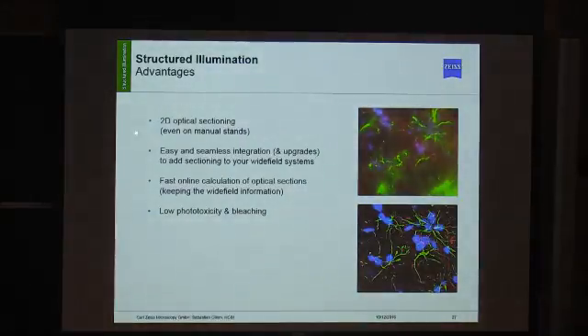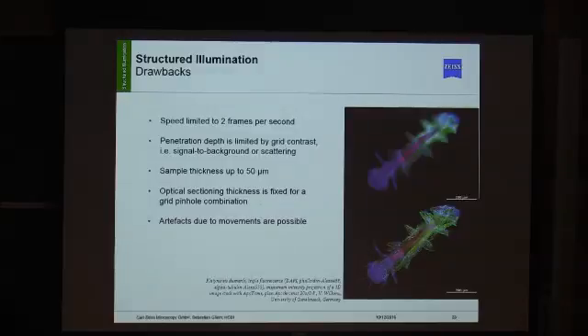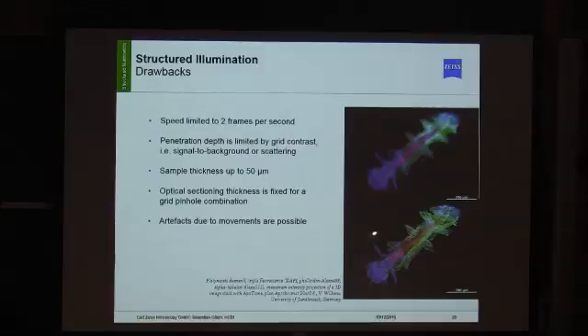The advantages of structured illumination are that you only need 2D optical sectioning, it's easy to use, relatively fast for acquiring sections, and it's very low with respect to phototoxicity and photobleaching as a camera-based system. The drawbacks: the system is relatively slow because you need multiple images per section — about 2 frames per second is the realistic maximum — so you cannot observe fast processes. Structured illumination is best suited when structures are fixed and nothing moves. Penetration depth is limited by grid contrast, and our recommendation is not to use samples thicker than 50 micrometers. Movement artifacts from vibrations can also be a problem.